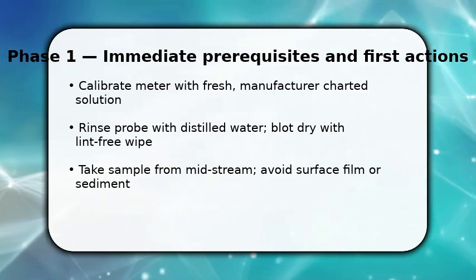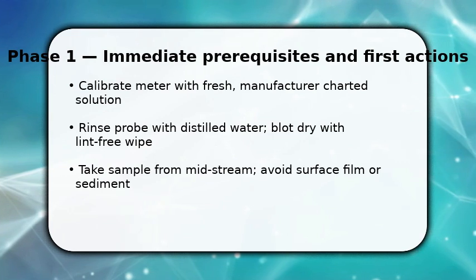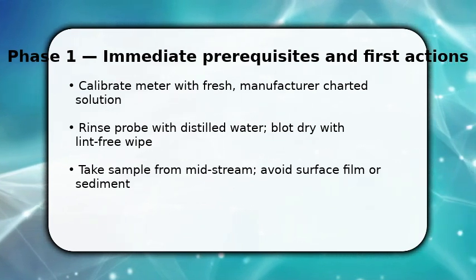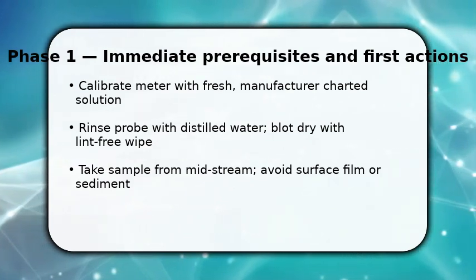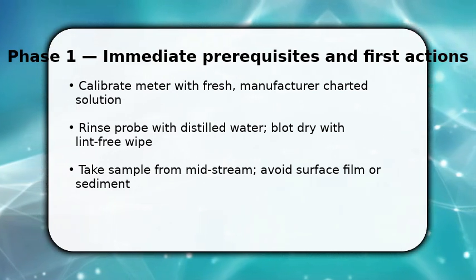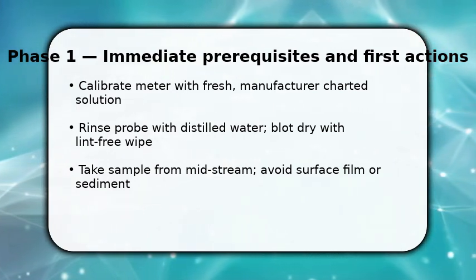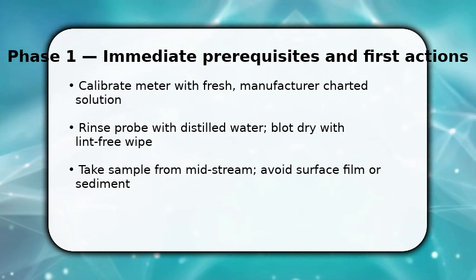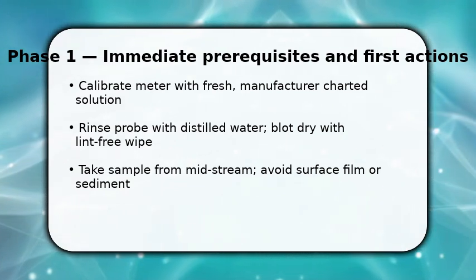Insert the probe and wait for readings to stabilize. You want consistent numbers over 10-30 seconds. Record TDS in ppm and EC in mS/cm, and note the sample temperature for accurate interpretation. Now interpret what you read.